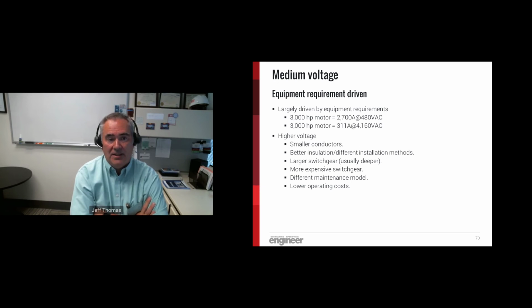But at 4160, it's 300 amps. Piece of cake. You can get 15 kV or 5 kV cables that do that all day long. The higher voltage means the conductors are smaller. The insulation is better and different, obviously, because the voltage is higher. The switchgear gets larger, usually deeper, and a lot of that has to do with the arc capability of the higher voltages. The switchgear, of course, is more expensive. There's a whole line of arc attenuating switchgear when you get into medium voltage class.